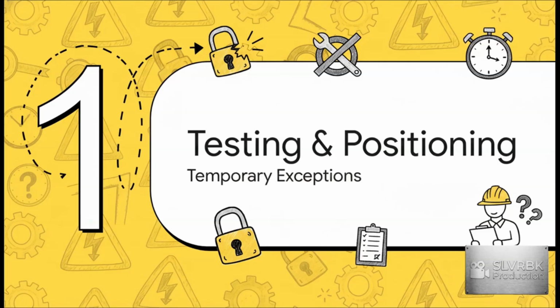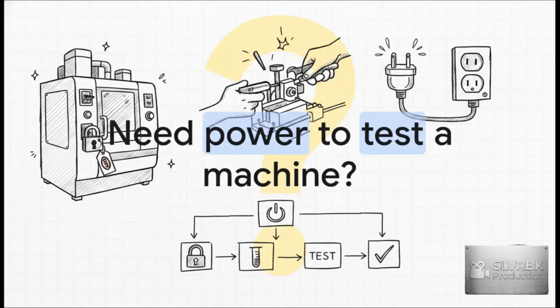Let's look at a major hurdle that comes up all the time. Okay, picture this. You're right in the thick of a complex repair. The machine is locked out, you swapped the bad part, but you actually need the power back on to see if your fix even worked. Or maybe you just need to jog a component into position. You obviously can't leave the locks on, but taking them off mid-job, that feels like breaking the cardinal rule of LOTO, right? Well, thankfully, OSHA gets it.